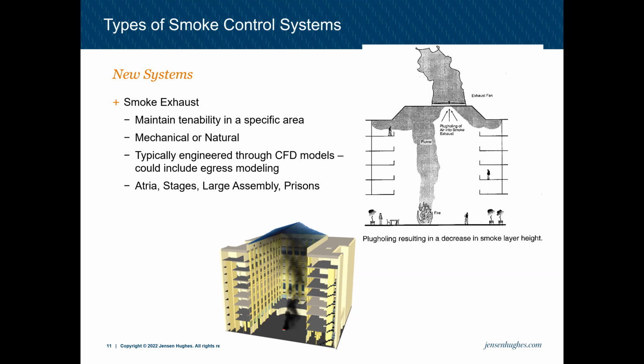So these smoke exhaust systems are usually by mechanical or natural means. Mechanical is usually giant exhaust fans or makeup air fans that will provide our air movement to get smoke out. And then we have natural means, which could be giant exhaust vents on our rooftop, and natural makeup air vents lower to the ground, such as doors or windows open, because we always need to replace the air that we're exhausting to physically move out the smoke.